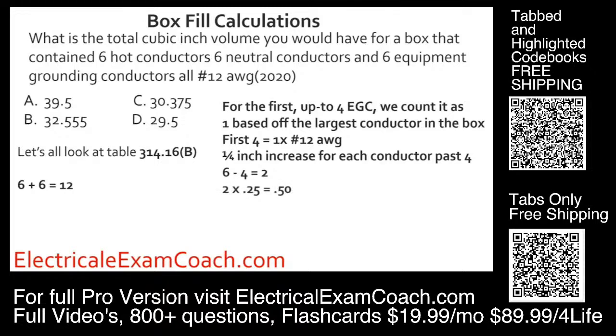For each one of those, it's going to be a 1/4 inch increase. Take 2 multiplied by 0.25, that equals 0.50. Then we have our 1 original. Then we have 0.50 add-on, so that gives us 1.50 grounds. We need to add that back to the 12, so we take our 12 plus our 1.50, then we multiply that by the individual volume for a number 12, which is 2.25, and we end up with 30.375.